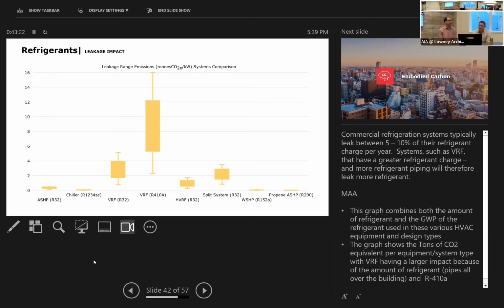It sounds really crazy that we talk about reducing carbon emissions, CO2 emissions, and they use CO2 as the refrigerant in the machine. But when you consider that the alternative to CO2 as a refrigerant is something that has a global warming potential of 2,000, a very small leak of CO2 in the overall scheme of things is tiny. So, how does the CO2 perform when compared to 410A and others? It's good. There are certain peculiarities to it. It operates at much higher pressure, so the piping has to be more robust, the fittings are more robust, and you need specialist maintenance people to look after the machine.